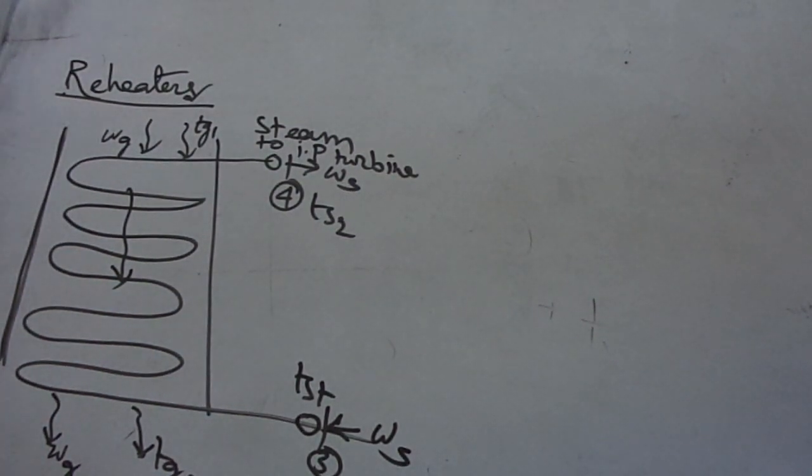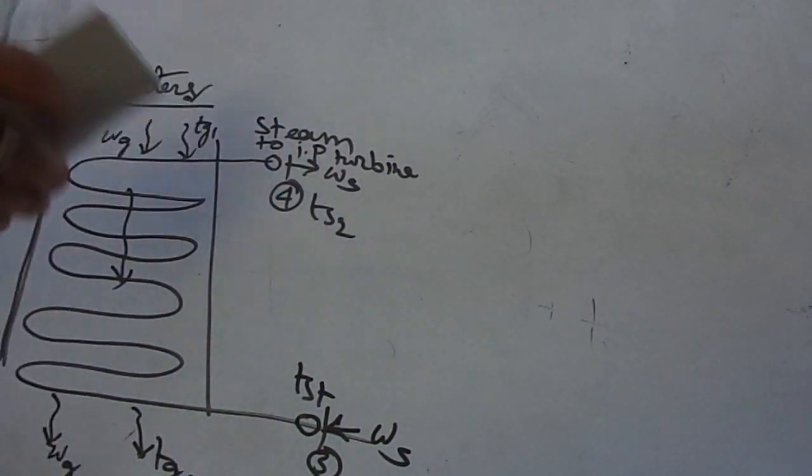Now, although the steam outlet temperature is about the same, the overall temperature is lower. Steam pressure is about 20 to 25% of that in the superheater. The pressure stresses are therefore lower, and a lower grade steel alloy is tolerated. In addition, larger tube diameter with lower stresses.